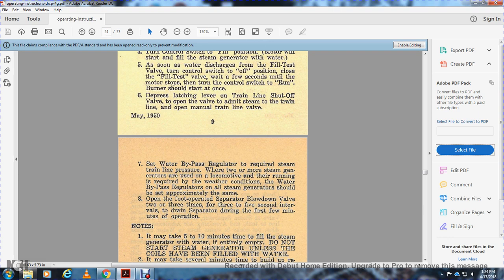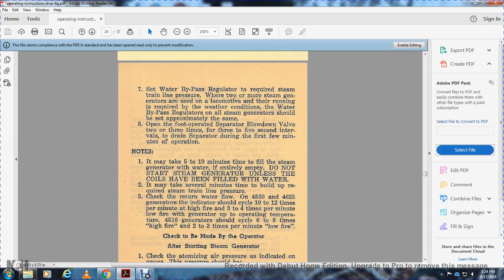Open the foot-operated separator blowdown valve 2 to 3 times at 3 to 5 second intervals to drain the separator during the first few minutes of operation. Note: it may take 5 to 10 minutes to fill an entirely empty steam generator with water. Do not start the steam generator unless the coils have been filled with water. It may take several minutes to build up the required steam train line pressure.